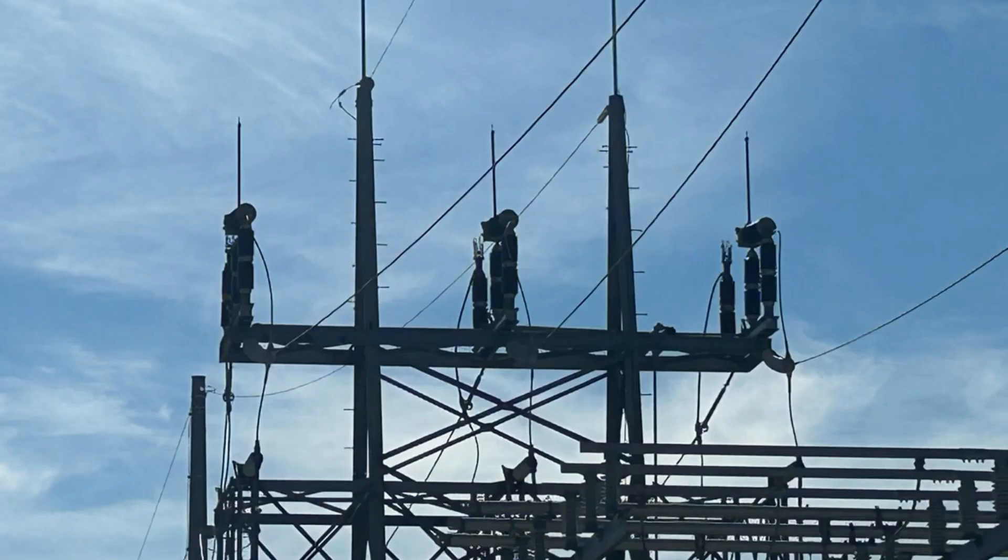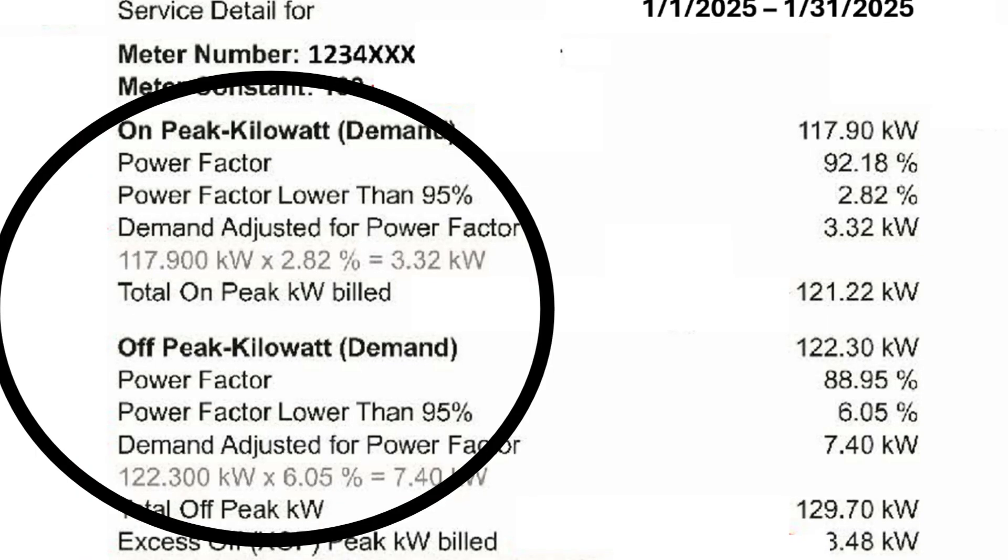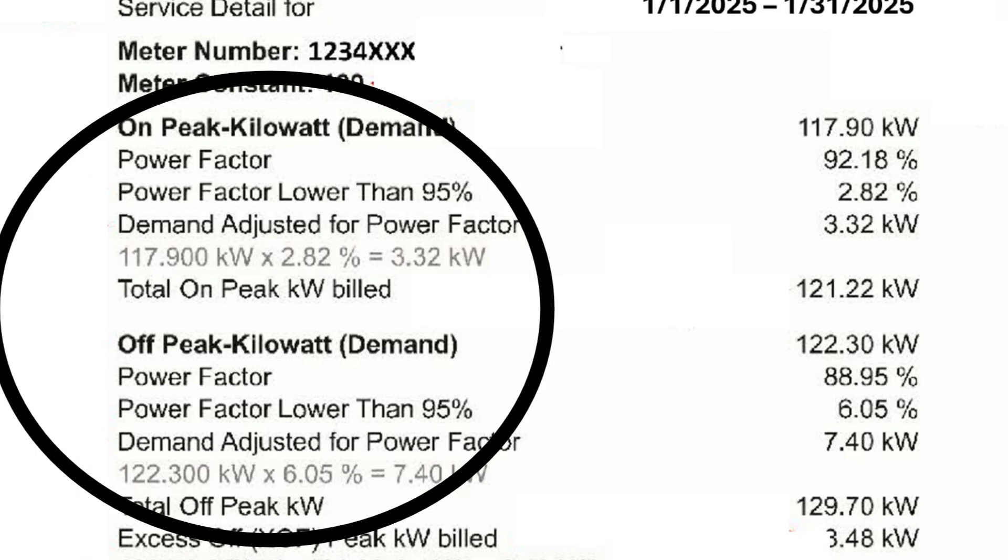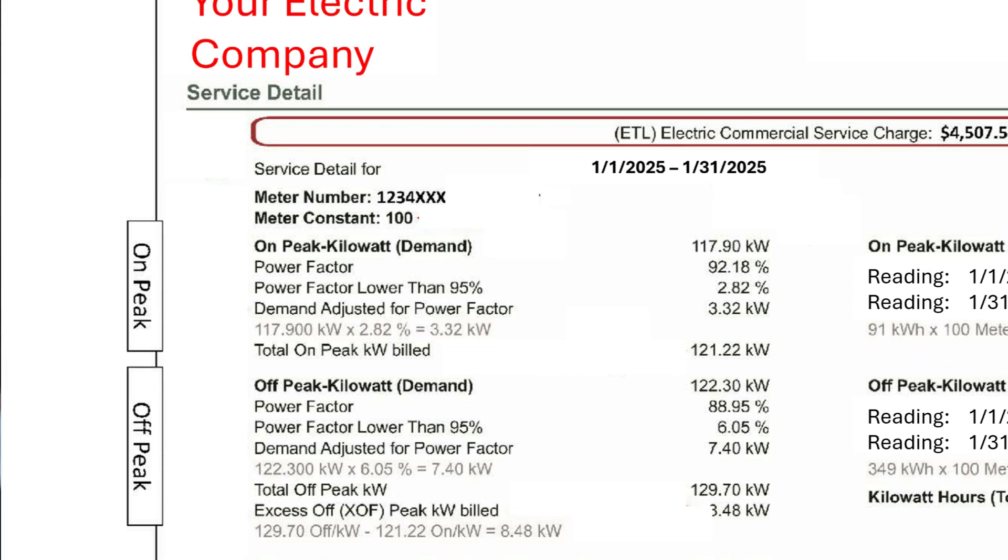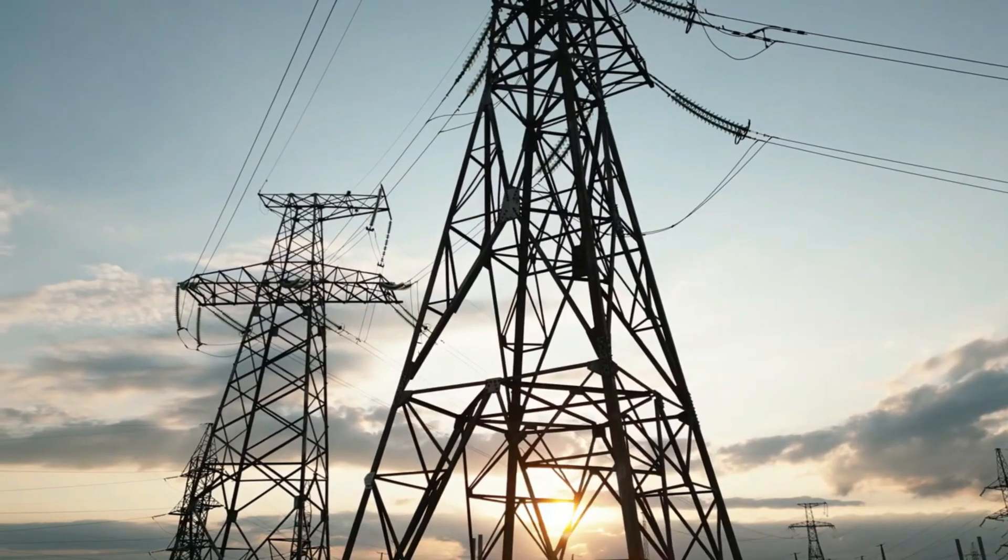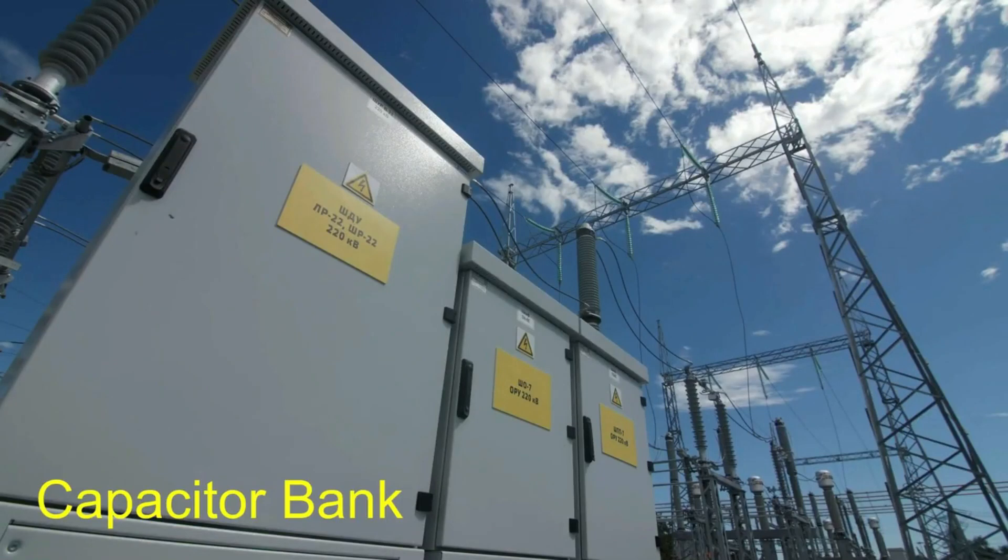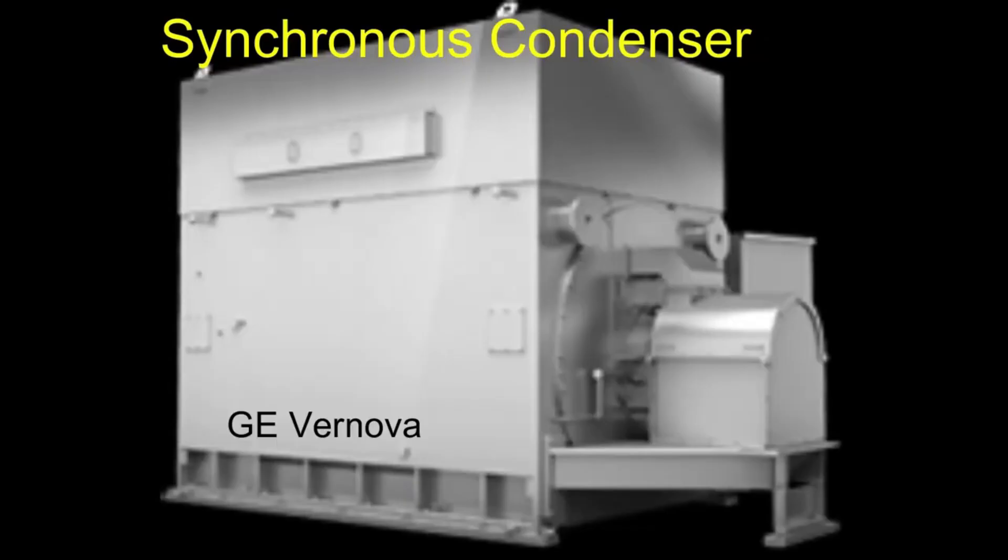To address this, utility companies often charge industrial and commercial customers with low power factors additional fees and penalties. These customers can improve their power factor by installing power factor correction devices, such as capacitors or synchronous condensers, which offset the reactive power in the system. By doing so, they reduce the overall current flow, lower energy losses, and they avoid costly penalties.